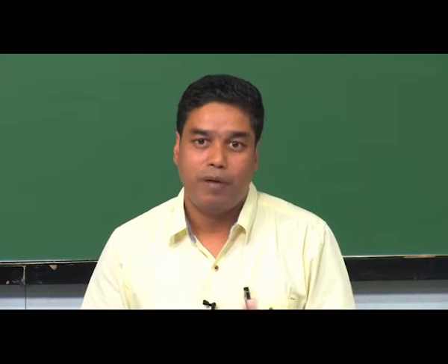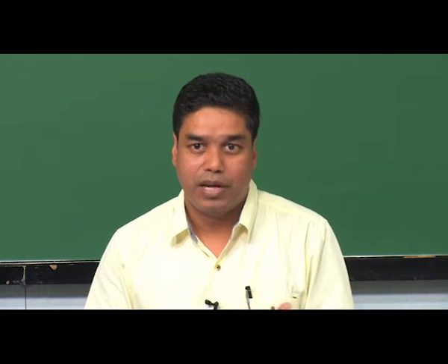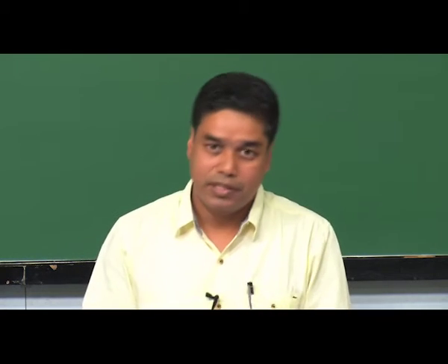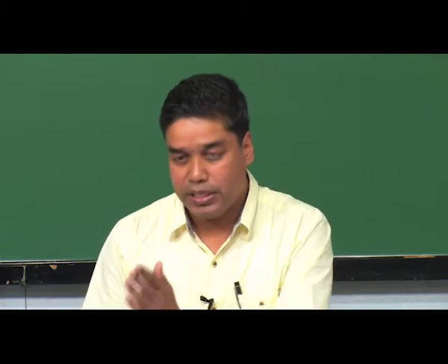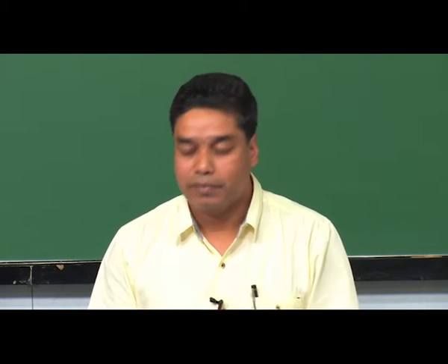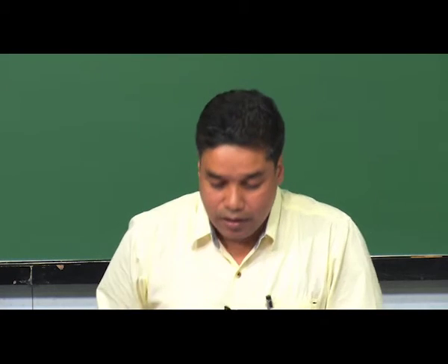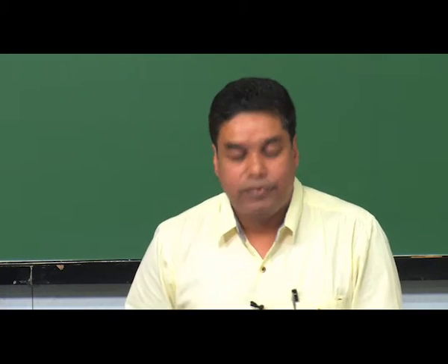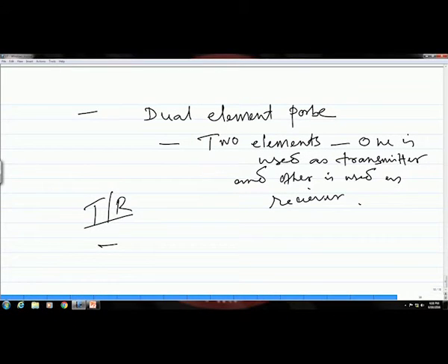So, there will be no problem in receiving it, because the fluctuations are not in the picture in this case, because a different element is receiving the echo which is coming out from the sample. Okay. So, this is another way of addressing the dead zone effect, and there is one more method by which you can address dead zone, that is by immersion testing.